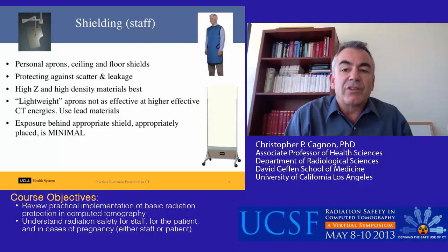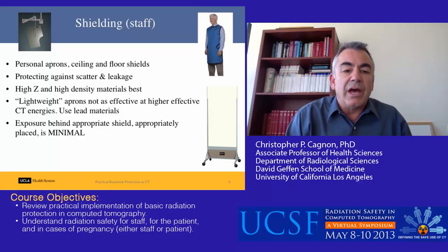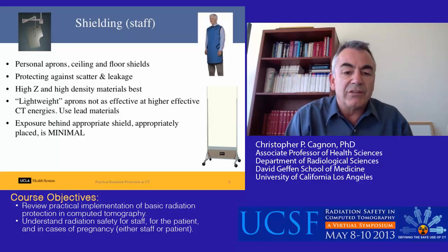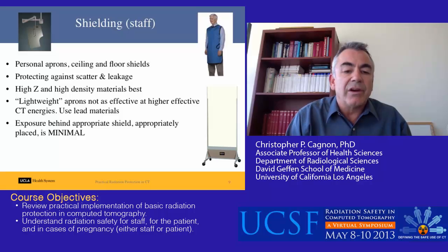We have to talk about shielding for the staff specifically. Shielding can consist of personal lead aprons, ceiling-mounted shields, and rolling floor shields — all for protecting against scatter from the patient and leakage from the x-ray tube assembly. High atomic number or high-Z, high-density materials work best. I caution against using lightweight aprons; they're not as effective at the higher energies used in CT, such as 120 kV. These materials use non-lead combinations — tin, barium, antimony — whose K-edge is not as effective at these higher energies. We recommend lead materials for CT shielding.